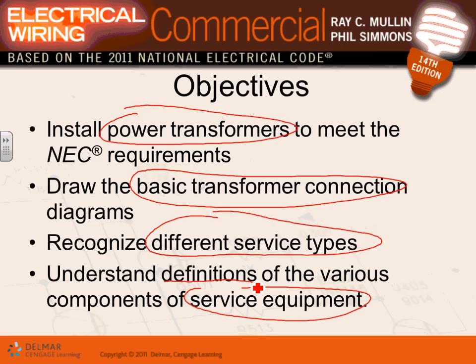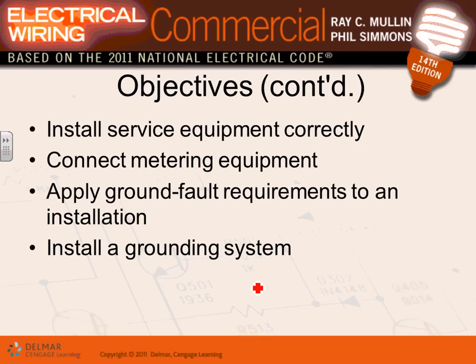We'll talk about service equipment, service disconnects, and service overcurrent protection devices. And this, Karen, is a fancy name for a big panel, the main panel in your building. That's really what it is, a big panel. The main panel in your building is called service equipment. It has to have a circuit breaker that acts as a disconnect and an overcurrent protection device. You guys have sized it. Our panel was what, 500 amp. That's it. So it's nothing new.